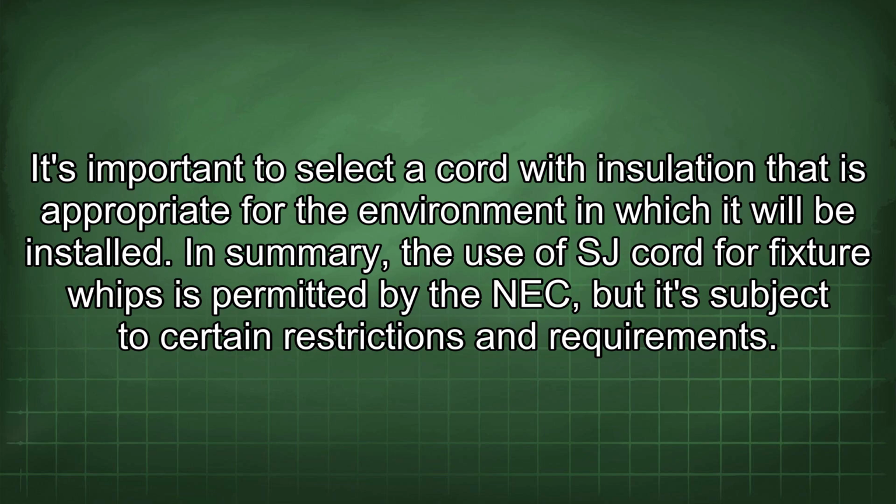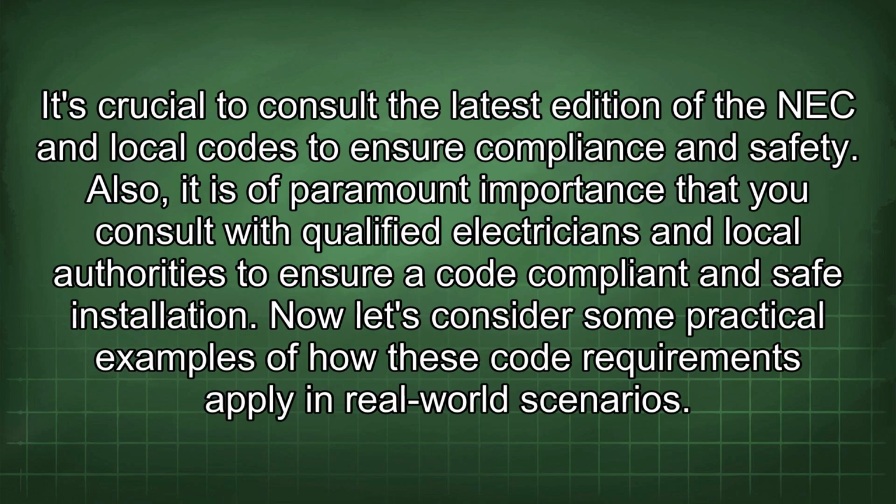In summary, the use of SJ cord for fixture whips is permitted by the NEC, but is subject to certain restrictions and requirements. It's crucial to consult the latest edition of the NEC and local codes to ensure compliance and safety. Also, it is of paramount importance that you consult with qualified electricians and local authorities to ensure code-compliant and safe installation. Now let's consider some practical examples of how these code requirements apply in real-world scenarios.